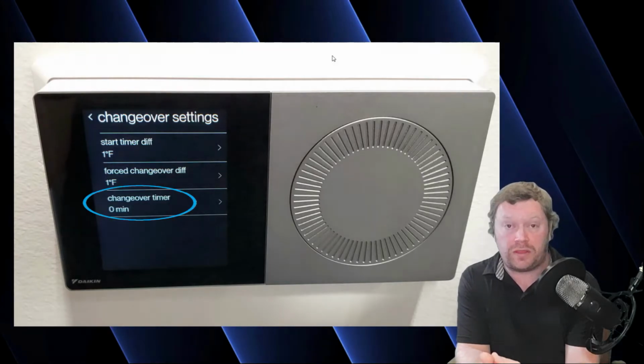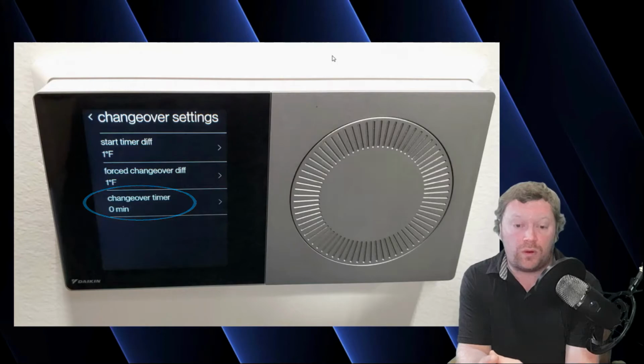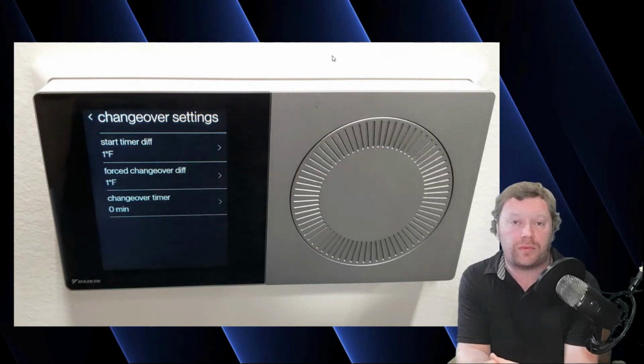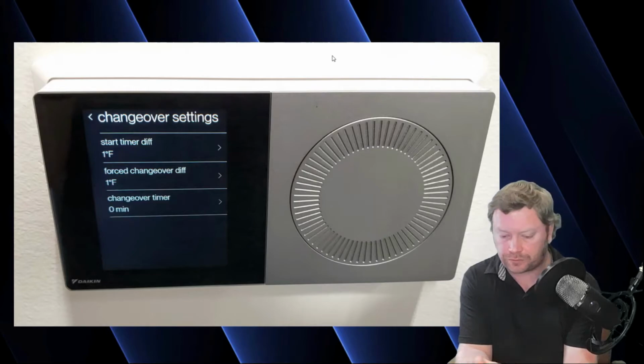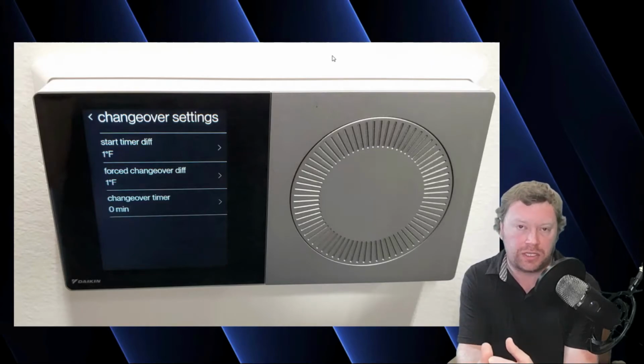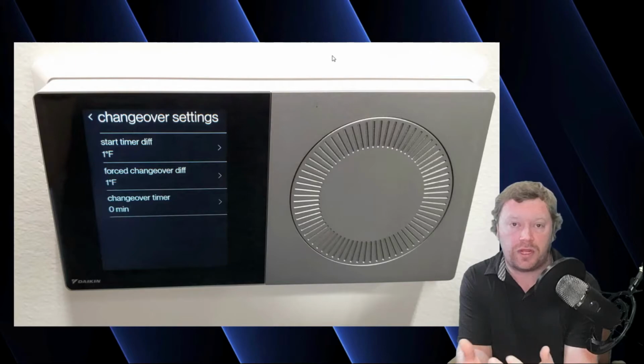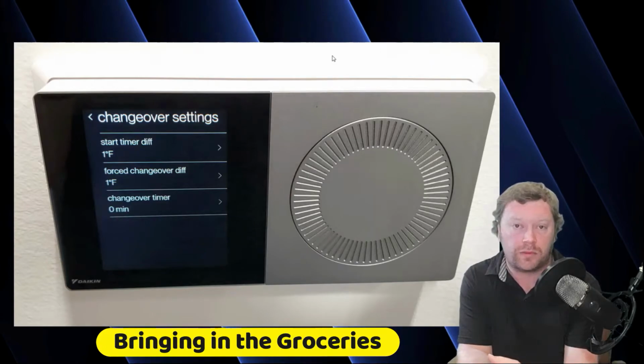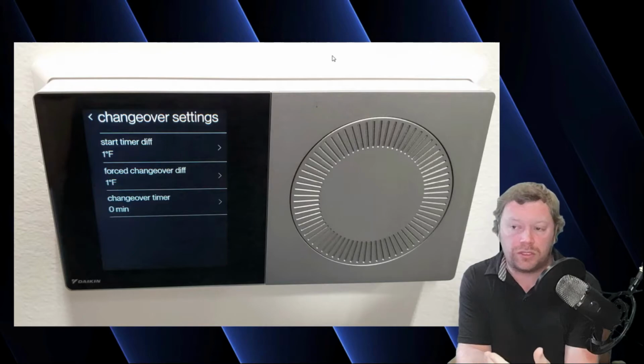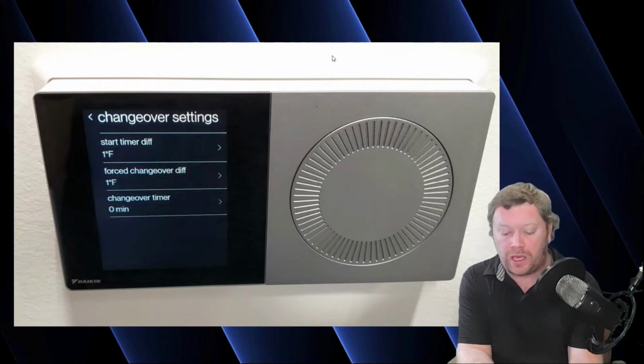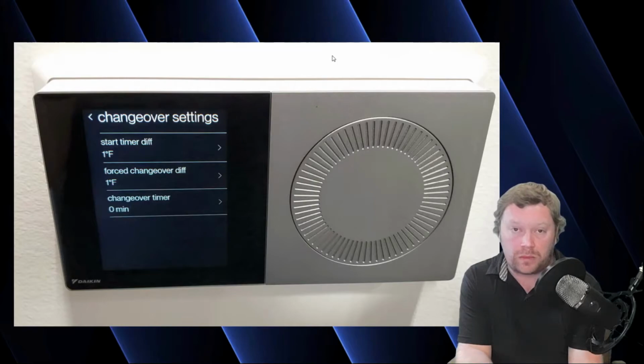And the idea with the timer is we don't want to immediately change the mode from heating to cooling or from cooling to heating in the event that the load changed in the space just temporarily due to external factors. You know, in locations like where I live, Pacific Northwest, generally we don't want our thermostat to be switching modes if we opened a door or if we opened a window for some temporary relief. So what I'll do typically is take that changeover timer and change it to 15 minutes or 30 minutes. So that way I have a little time buffer.